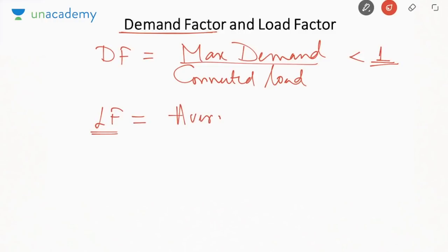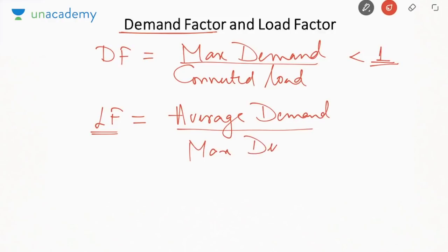It is average demand by maximum demand. This is one of the most important factors. This you must remember always. Okay. So now this factor will always be less than 1 because average will be less than maximum.